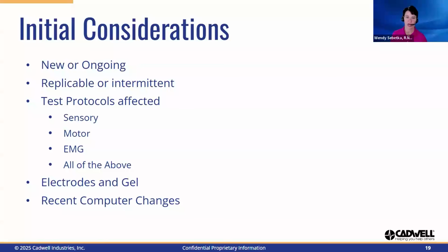After multiple uses, unseen damage may have occurred and replacement is inevitable. Even with increased frequency of disposable electrodes, we shouldn't discount our electrodes as a cause for noise. Expiration dates should be noted as the gel on the electrodes may deteriorate, decreasing the integrity of our electrodes. The purpose of the gel is to increase the conductivity between the surfaces. To maximize this effort, it is imperative that you are using non-expired gel that includes conductive properties.